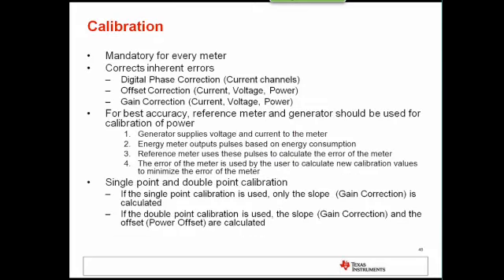In order to achieve good accuracy, meter calibration is necessary and is mandatory for every meter. Meter calibration corrects for any inherent errors. There are multiple types of calibration that can be performed. There's gain correction, there's offset correction, and there's also digital phase correction. Digital phase correction is used to account for any additional delay that's not due to the nature of the load. The reason this is important is that if there's a load, especially with a lower power factor, this delay could more adversely affect accuracy.